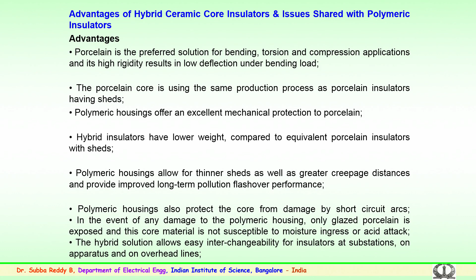The hybrid solution allows easy interchangeability of insulators at substations, on apparatus, and also on overhead lines. Replacement of insulators, bushings, post insulators, hollow core insulators, and overhead transmission line insulators is comparatively easier compared to ceramic or glass type technology. That is one of the major advantages of going in for hybrid technology.